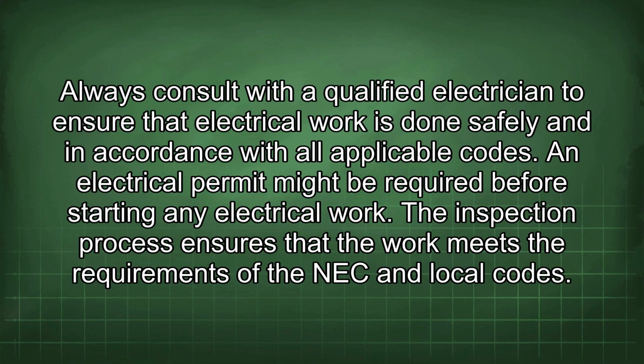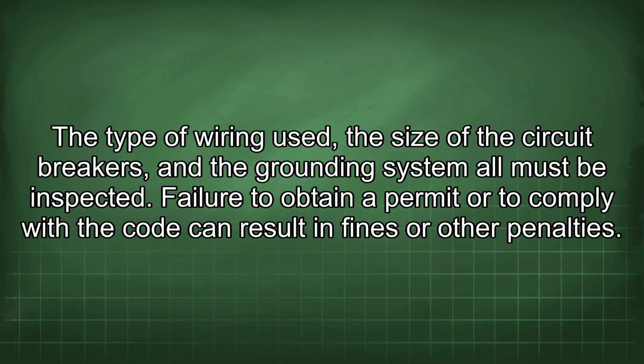Always consult with a qualified electrician to ensure that electrical work is done safely and in accordance with all applicable codes. An electrical permit might be required before starting any electrical work. The inspection process ensures that the work meets the requirements of the NEC and local codes. The type of wiring used, the size of the circuit breakers, and the grounding system all must be inspected. Failure to obtain a permit or to comply with the code can result in fines or other penalties.